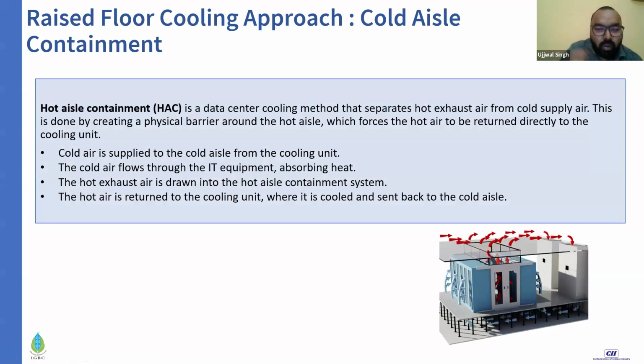Similarly, the opposite of cold air containment is hot air containment, where instead of capturing the cold air inside a containment, you are capturing the exhaust hot air inside a containment, and the overall room is filled up with cold air.